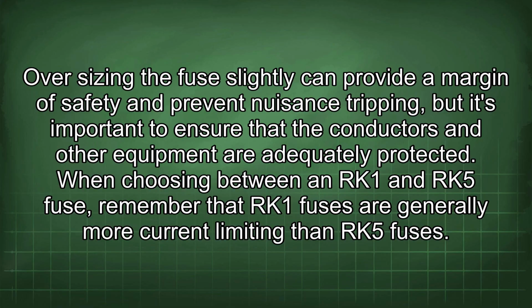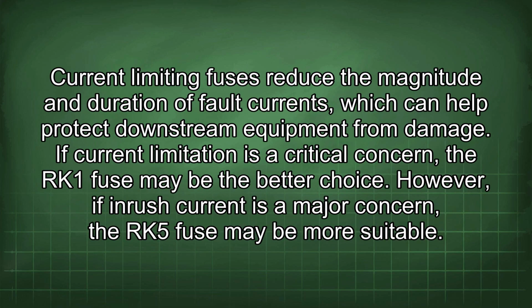When choosing between an RK1 and RK5 fuse, remember that RK1 fuses are generally more current limiting than RK5 fuses. Current limiting fuses reduce the magnitude and duration of fault currents, which can help protect downstream equipment from damage. If current limitation is a critical concern, the RK1 fuse may be the better choice. However, if inrush current is a major concern, the RK5 fuse may be more suitable.